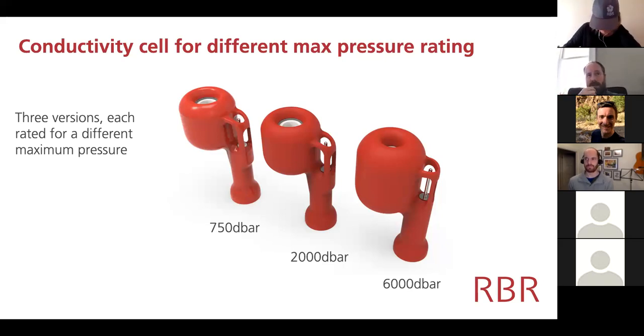In fact, if you ever come across a broken one, they're fascinating to take apart. The membrane is about 10 microns. And so it's almost like you look at it and you dent it. Please don't ever stick Q-tips, screwdrivers, fingers, other things in there to clean it off. Leave it overnight in vinegar and then rinse it with fresh water. We find that there's not much that resists that.